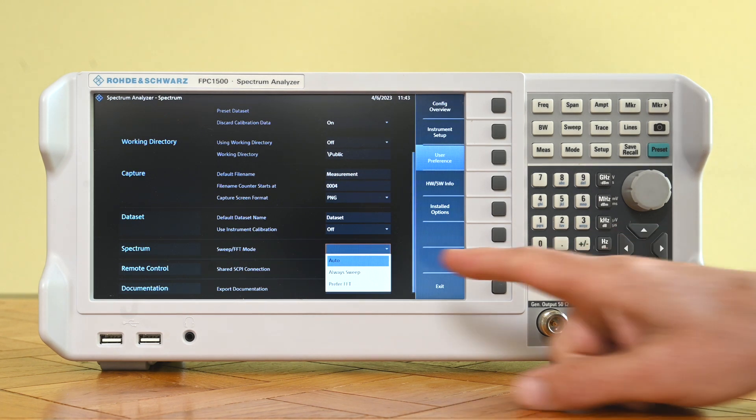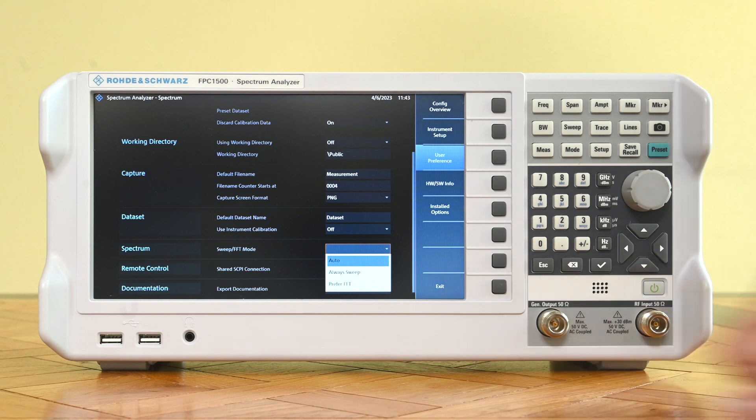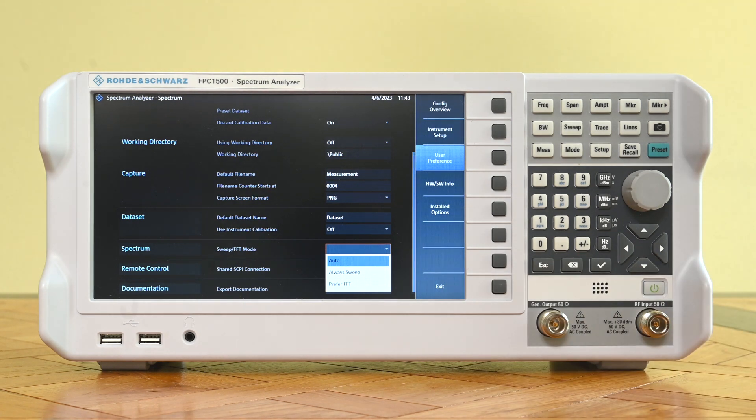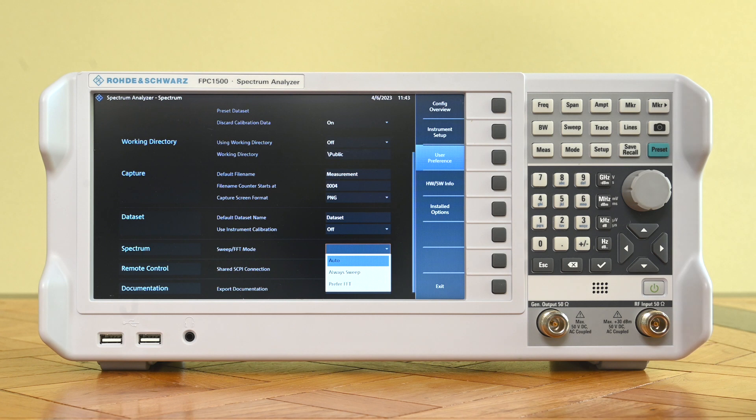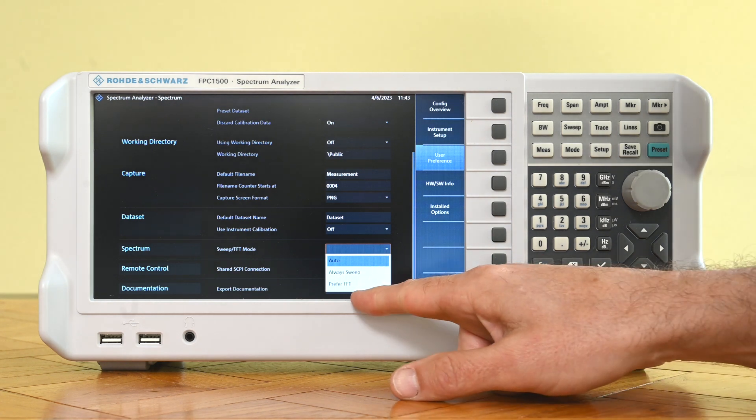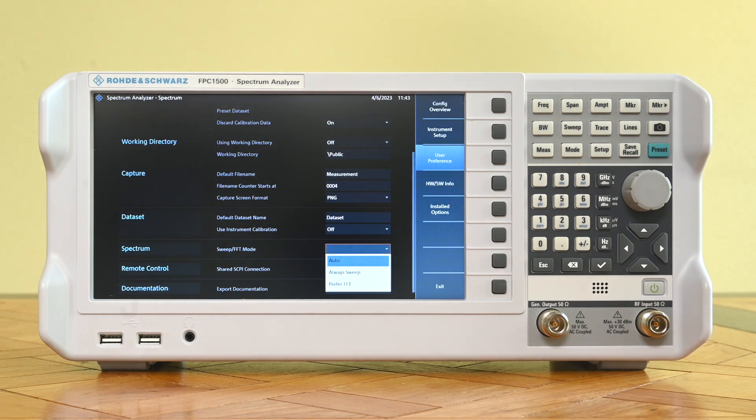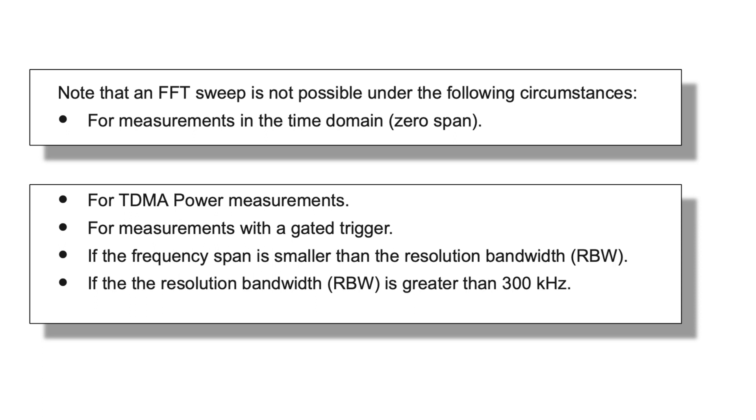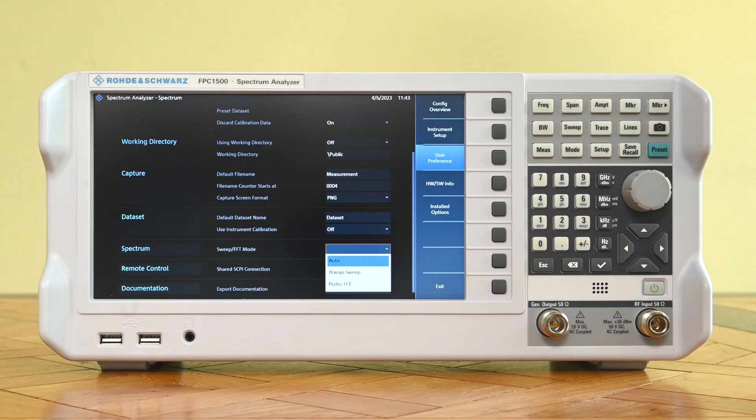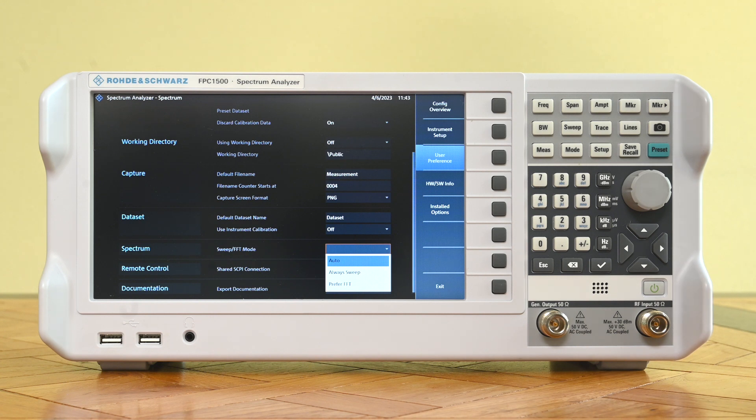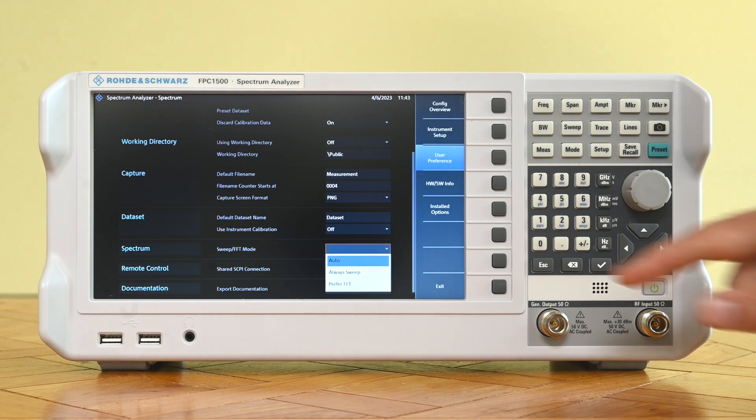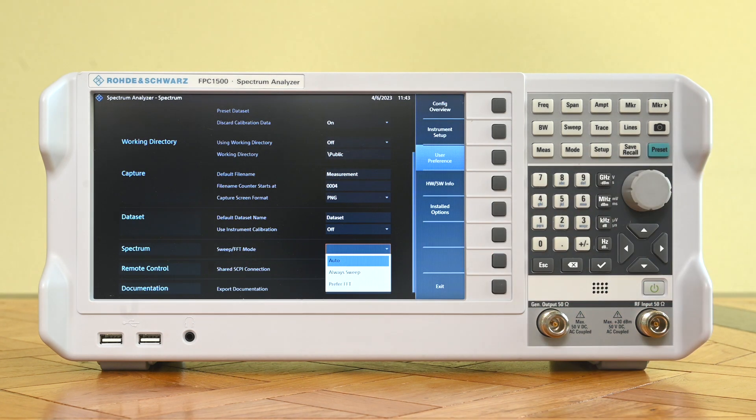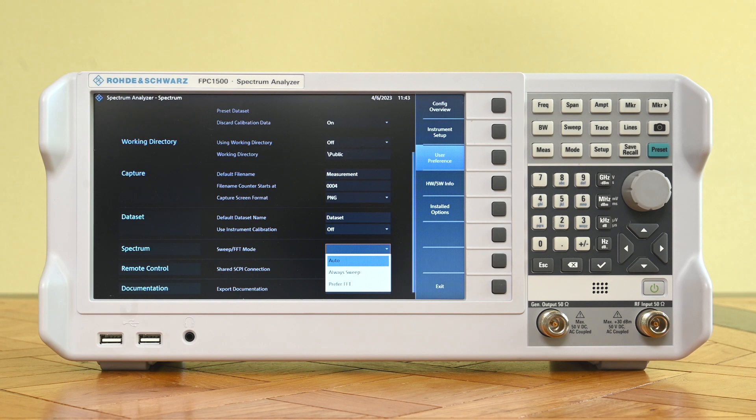So we have to look a little bit more carefully at the meaning of these three categories to fully understand what we're going to see on the screen. Now always sweep, that is kind of easy. That always forces the device into sweep mode. Prefer FFT means that the device will use FFT if possible. That's why it doesn't say always FFT but it says prefer FFT. And in the user manual we actually find additional information which explains in which particular cases FFT is possible or not. I'm going to show them right now on the screen. If we're operating in one of the modes in which FFT is not possible then it will run in sweep mode even if you choose prefer FFT. And then in the auto mode basically the device automatically chooses the fastest option of the both.